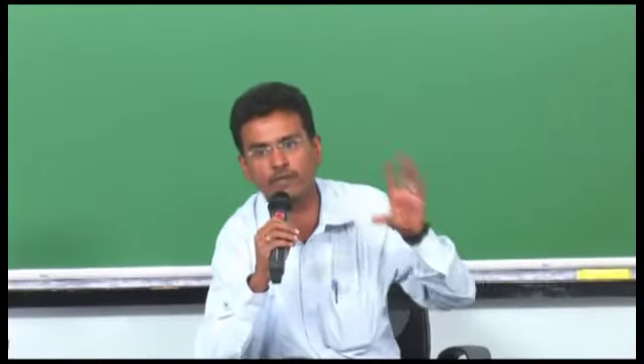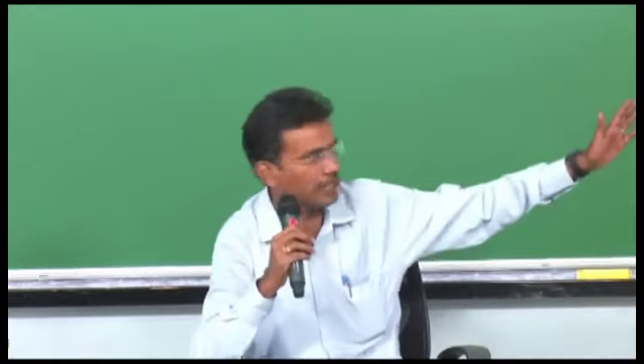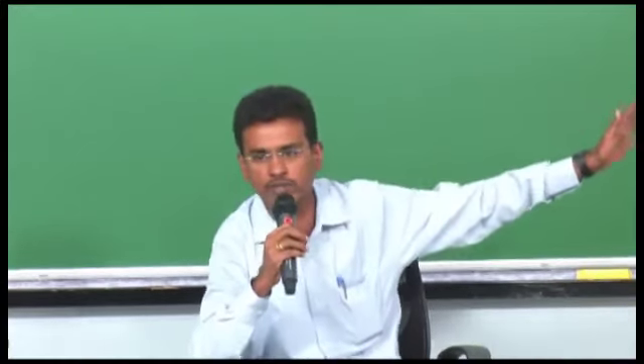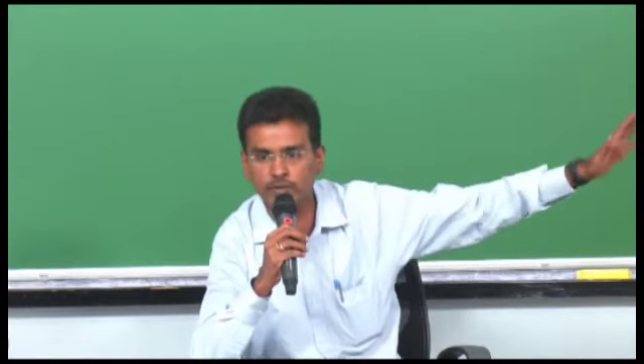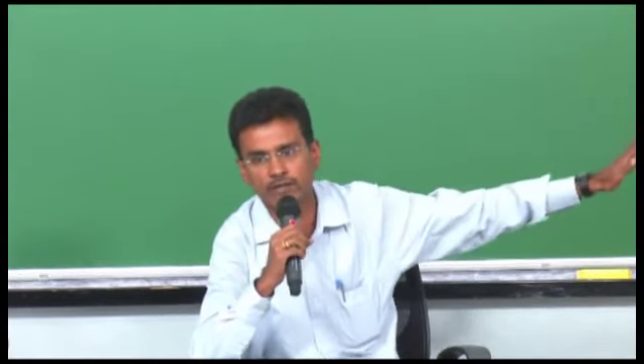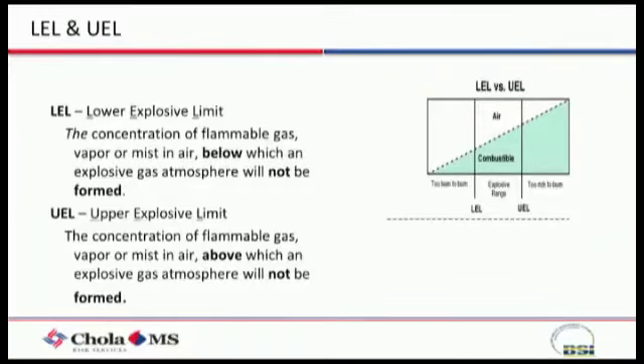But in hazardous area classification, we talk about LEL and UEL. When putting in a detector for LEL, they will set the value of LEL. Below LEL, no fire or explosion will happen. Above UEL also, fire or explosion will not happen. In between the range, between LEL and UEL, fire will happen. That's the concept you need to understand.